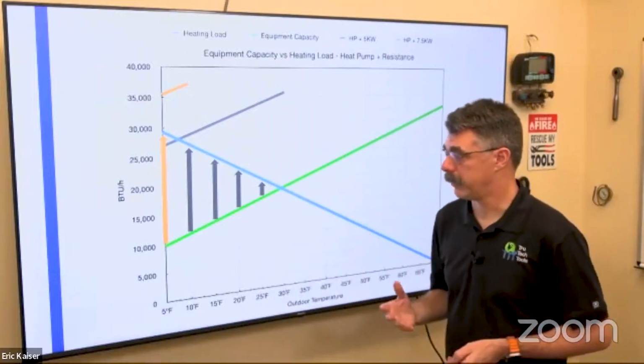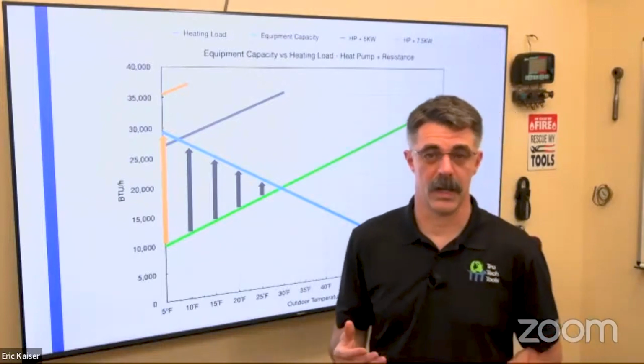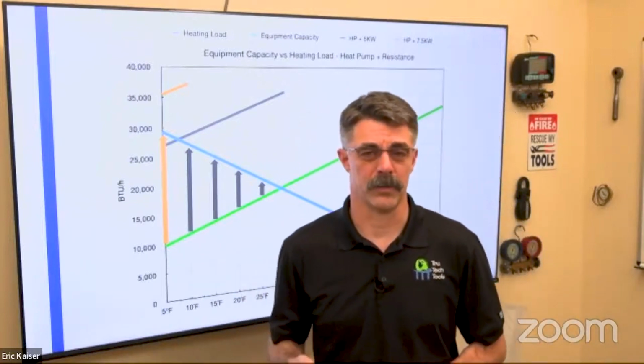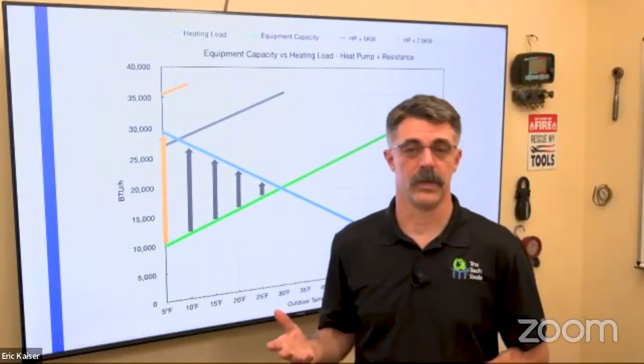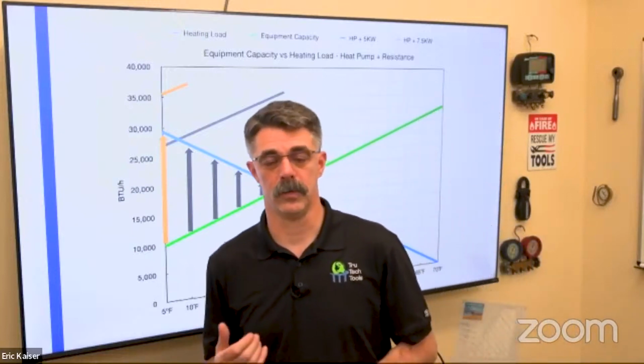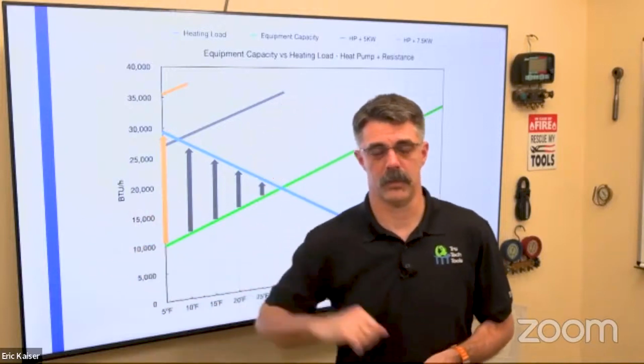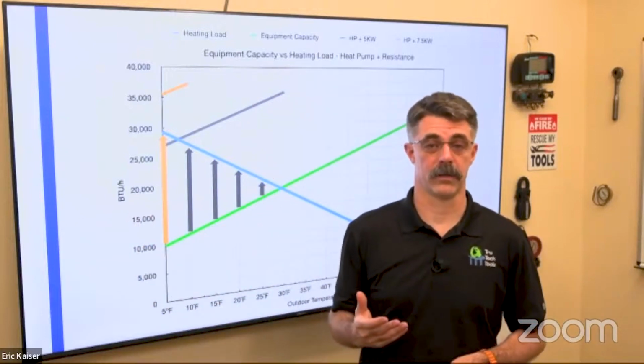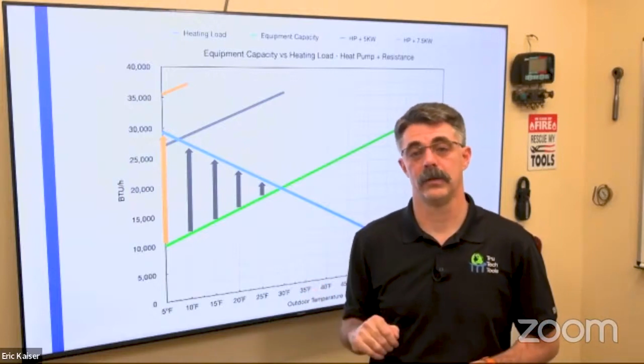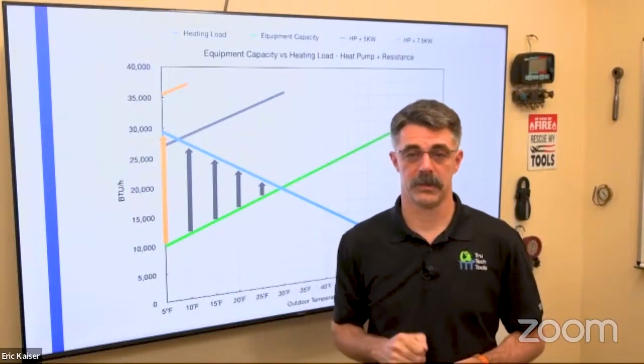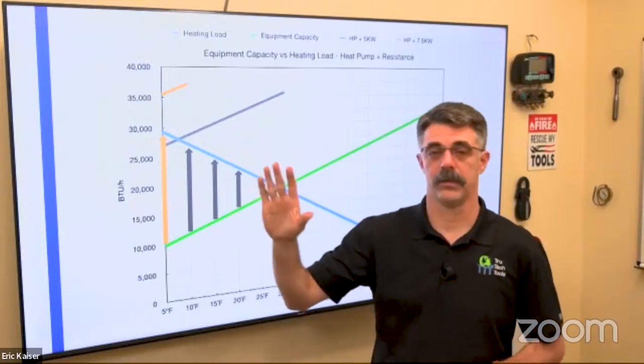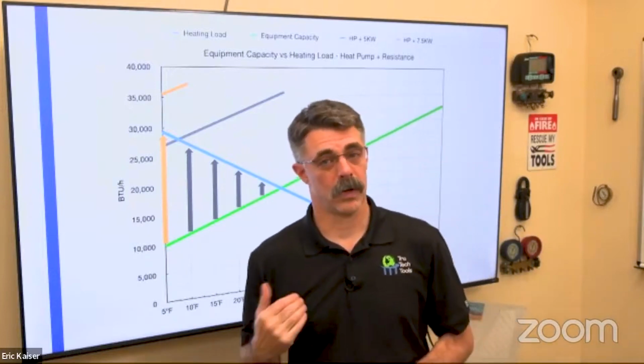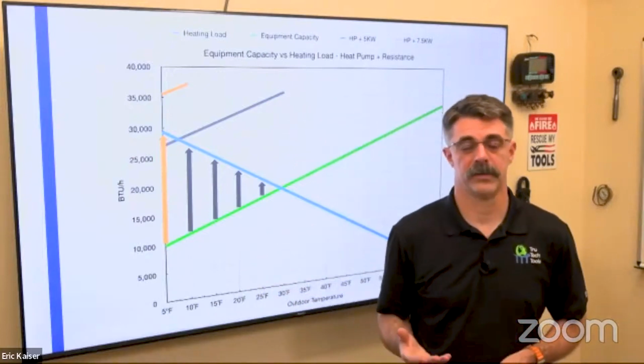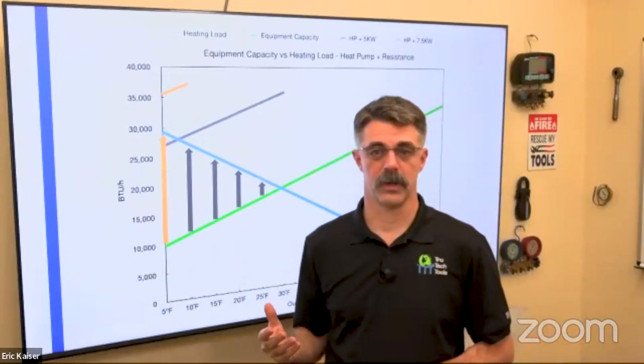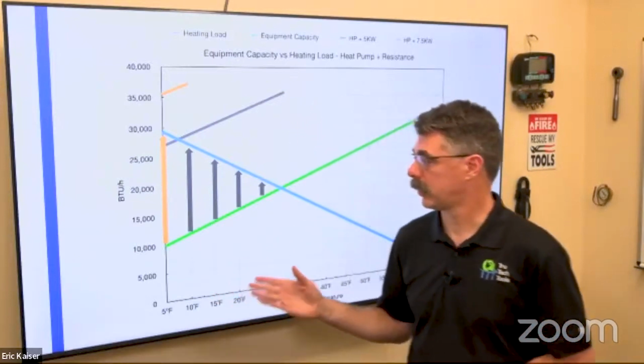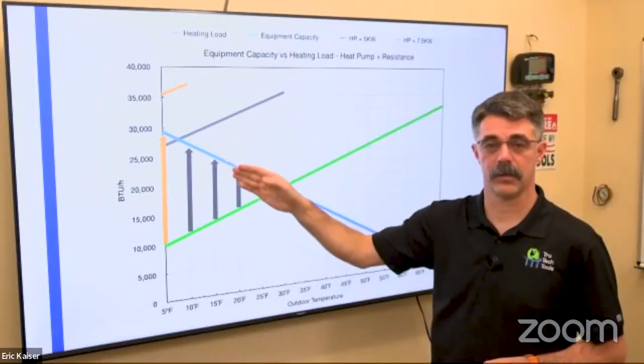Okay. The first job that I had, my boss had done a house way before I started working there. In all, he only did one house in this new addition. All the other houses were done by another contractor. And the other contractor would tell their customers, hey, when it gets cold out, go over there and switch to emergency heat. Just run your electric resistance heat. Don't run the heat pump. Well, my boss, he understood heat pumps. He understood how to set them up. And he put a special switch on there. And when it got to a certain outdoor temperature, it added in some electric resistance heat while it kept the heat pump running.